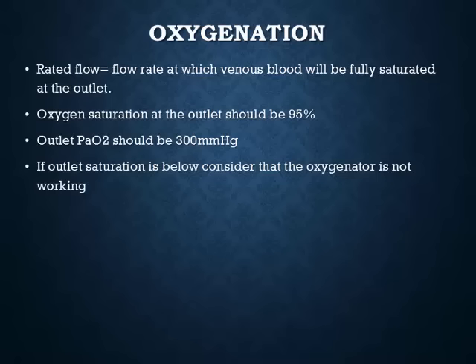For oxygenation in the oxygenator: the package insert provides a rated flow measurement — the flow rate at which venous blood will be fully saturated at the outlet for a given hemoglobin. For example, if your patient has a hemoglobin of 12% at this cardiac output, the expected post-oxygenator PaO2 is 350. If it's not meeting the package requirement, the oxygenator may be faulty.